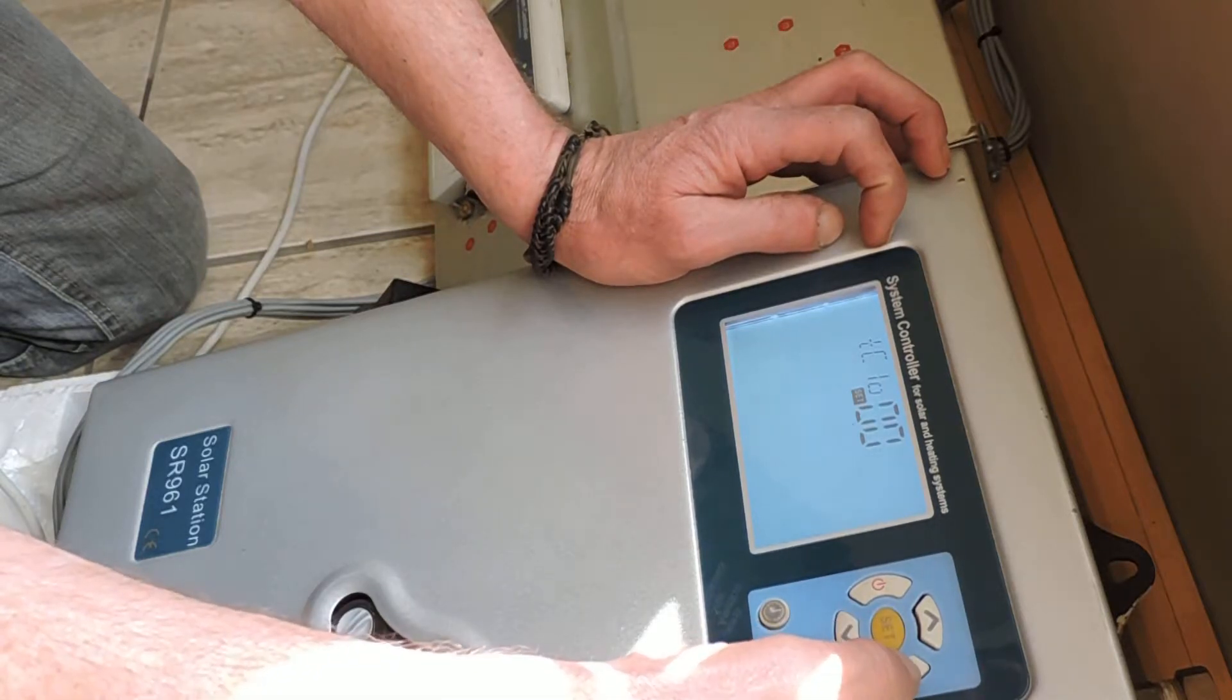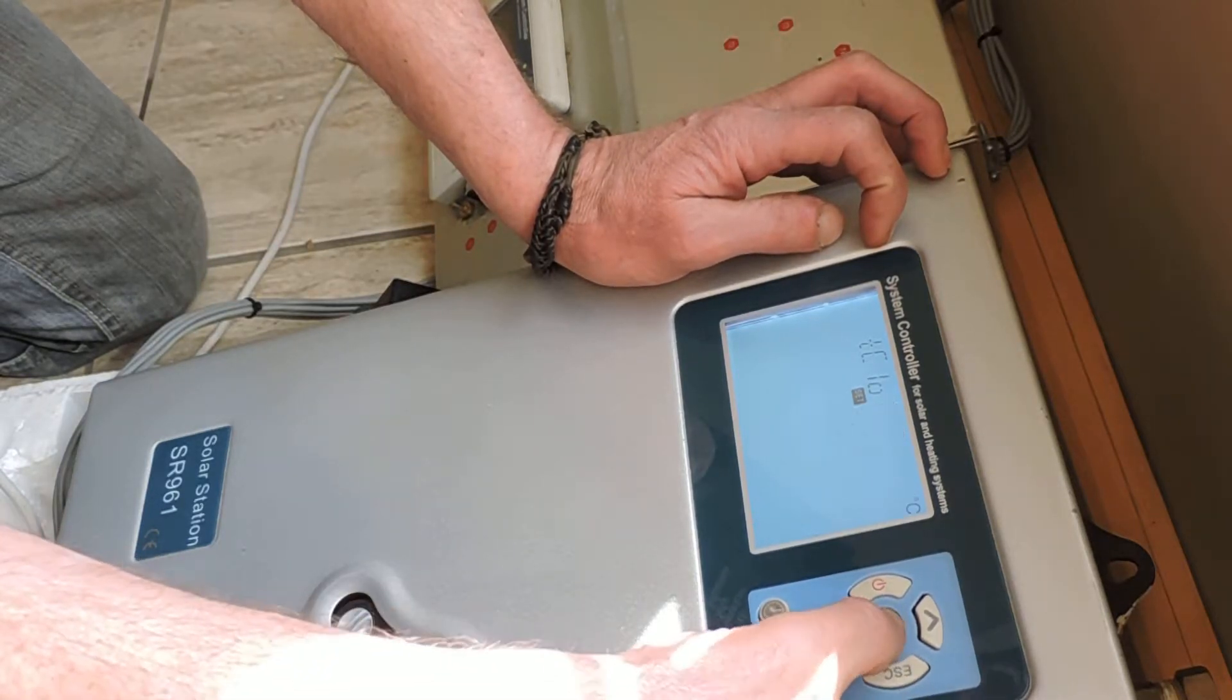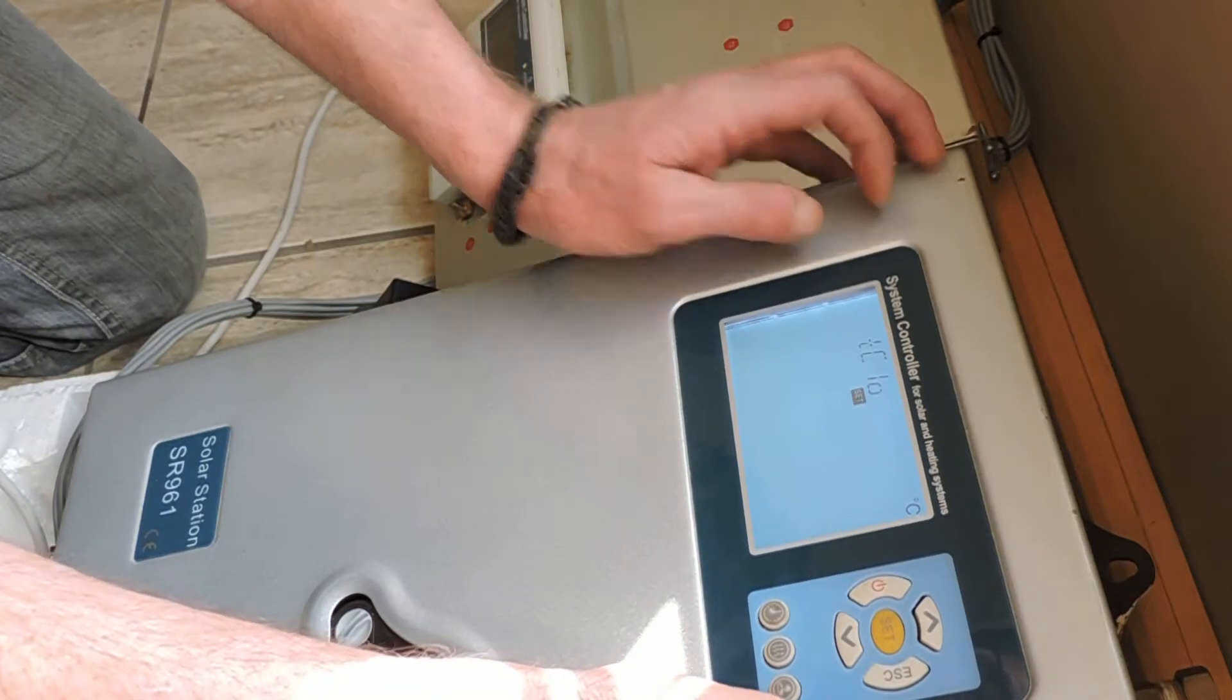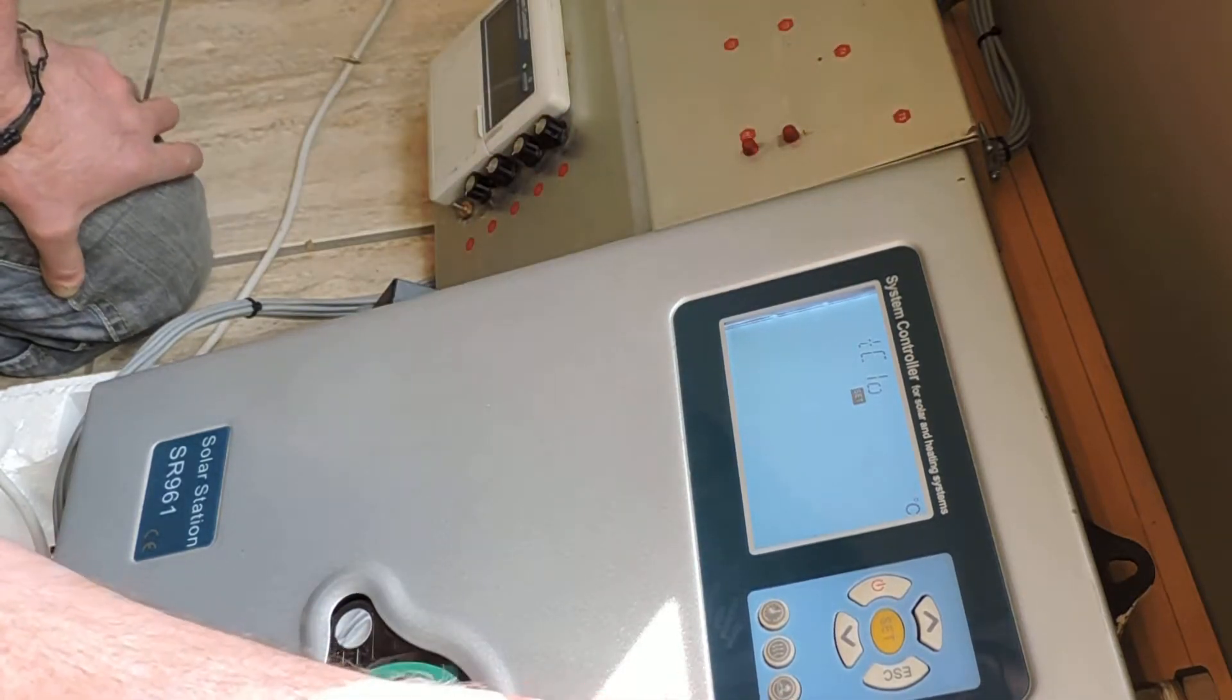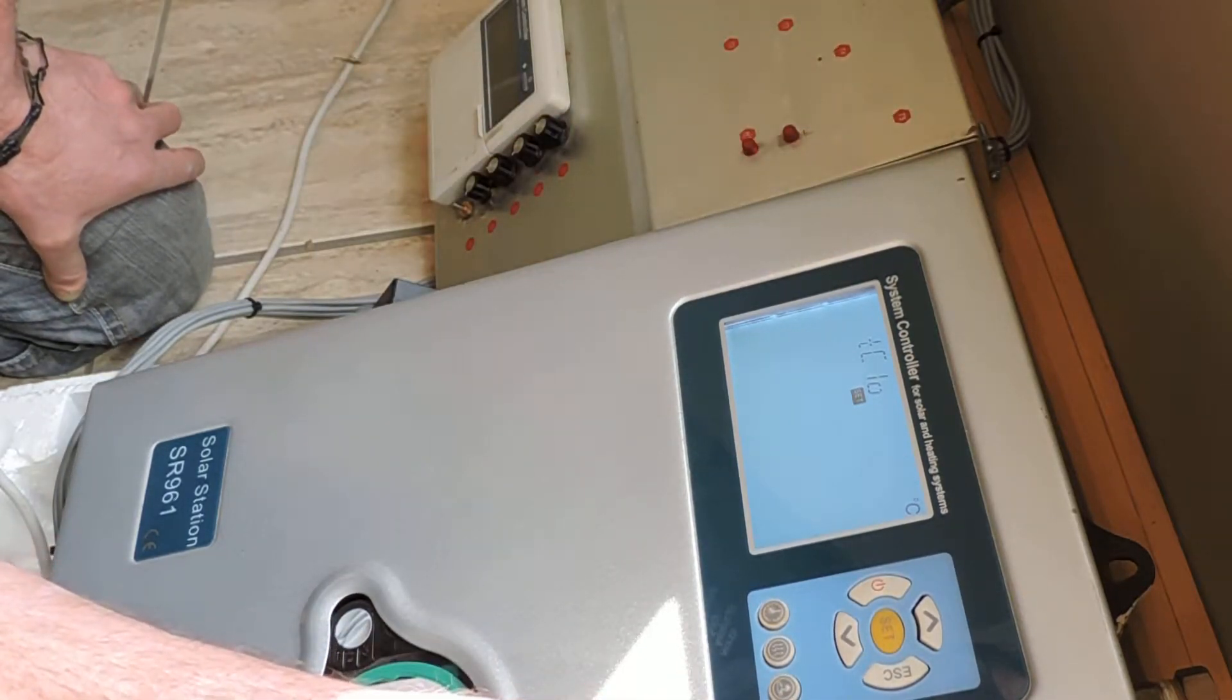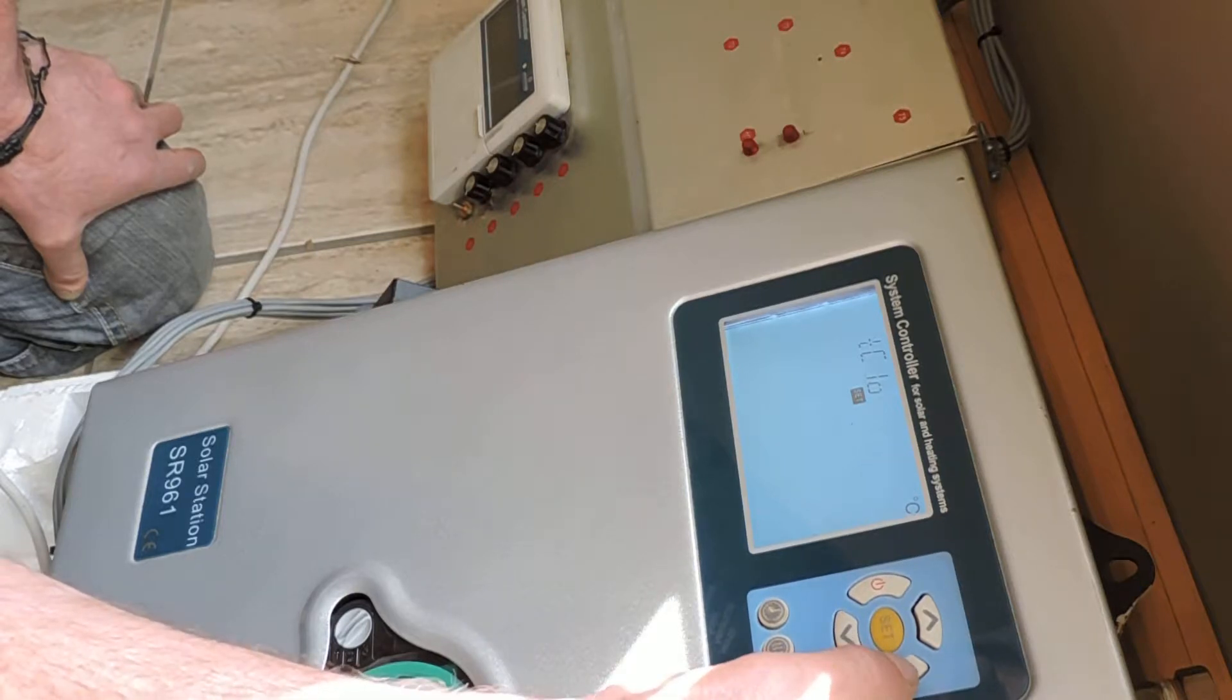When we say set, it is going to ask for a temperature. If the temperature is lower than 35 degrees, the circulation pump starts running. We are going to use that one.